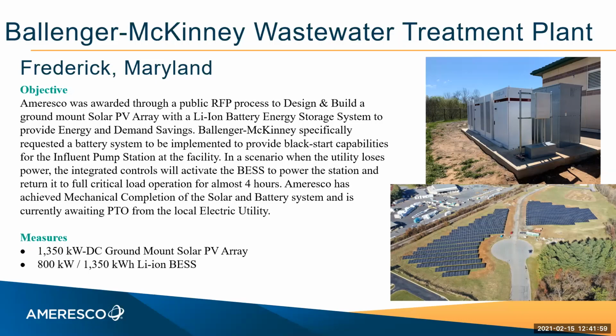The project is at the forefront a microgrid, with the goal of having the solar provide daily energy savings for the facility, as well as charge the battery, which is outfitted with controls to black start the wastewater treatment pumps. From there, it has about a 4-hour lifespan where the battery can fully power the system from the renewable energy before the grid is able to turn back on. Again, we finished mechanical completion earlier this year, and are currently waiting for PTO from the electric utility.